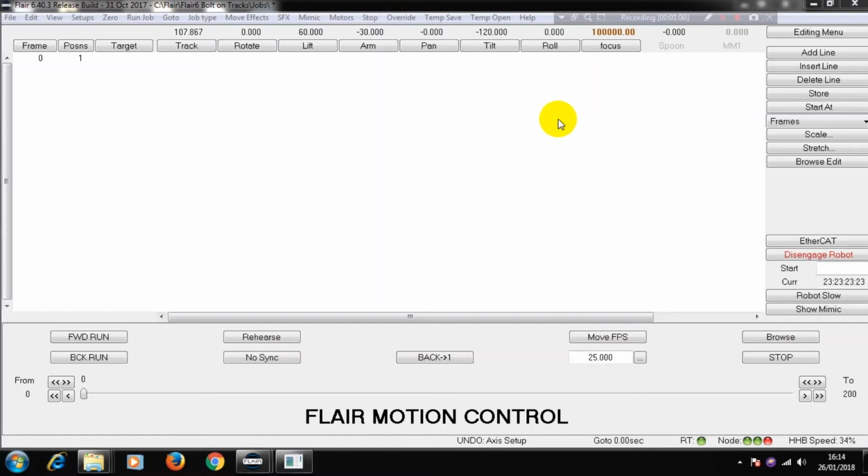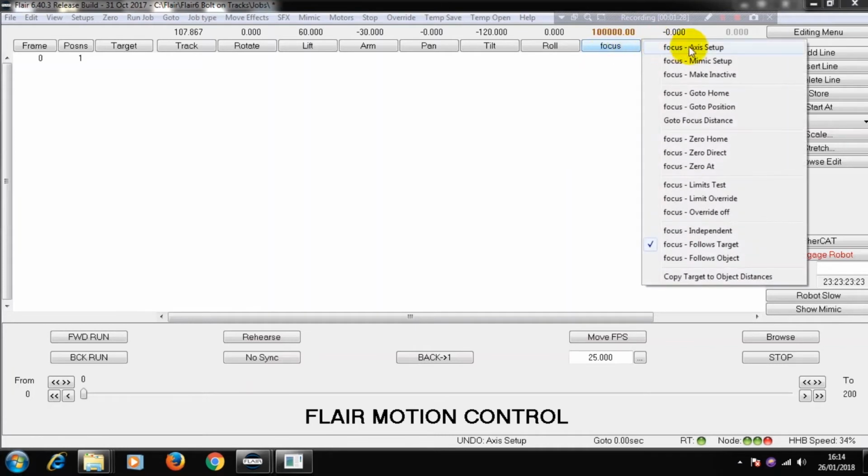With the Bolt robot, the arm itself, there are encoders on the axes that are absolute. And these encoders mean that when we turn on the machine, it knows where it is, and those motors can go to the home zero position easily. Other axes need zeroing.